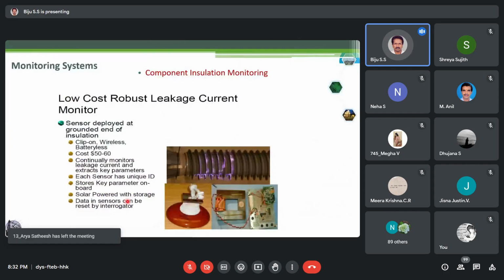Now again, monitoring the insulation materials, leakage through the materials, that can also be monitored nowadays. You have wireless batteryless sensors available now, which you deploy at the grounded end of the insulation. It will monitor any leakages there and give an alarm. So even the insulators in your substation yard or in transmission lines can be easily monitored.